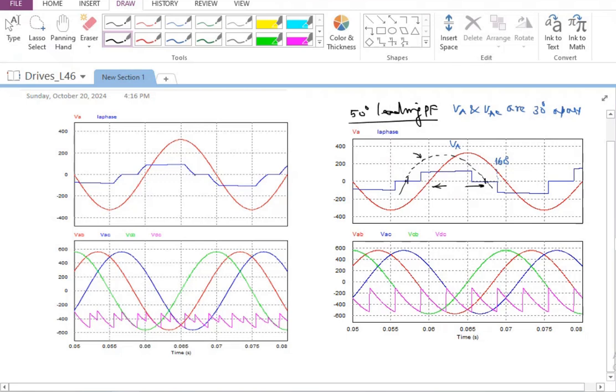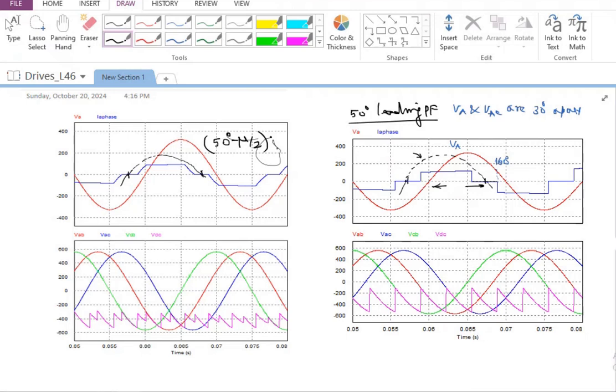Whereas if you look here for the same firing angle but with commutation overlap, if I show the zero crossing somewhere here, the waveform will look somewhat like this. You can see how the waveform changes. So this is going to be 50 minus mu by 2, that is 50 degrees minus mu by 2, which happens to be the leading angle as far as the fundamental current and voltage are concerned.